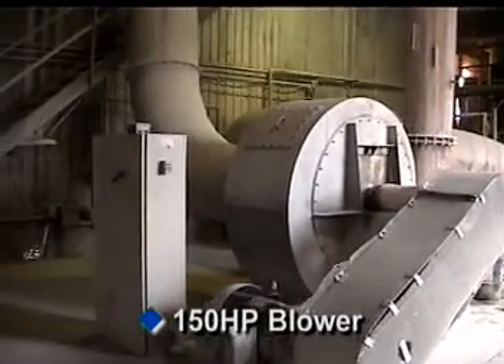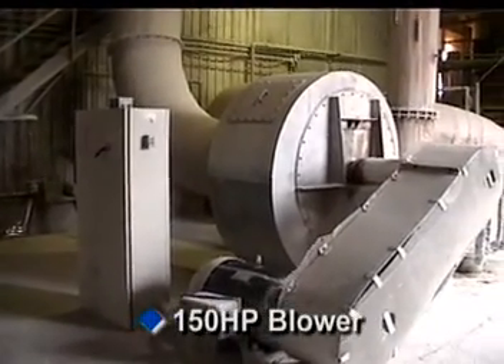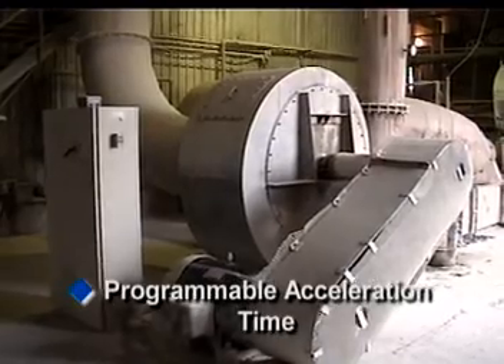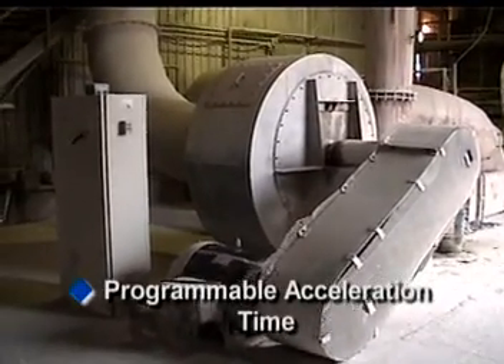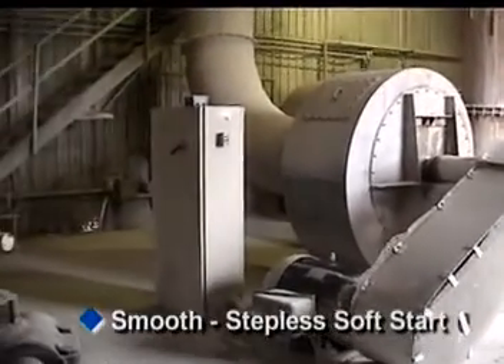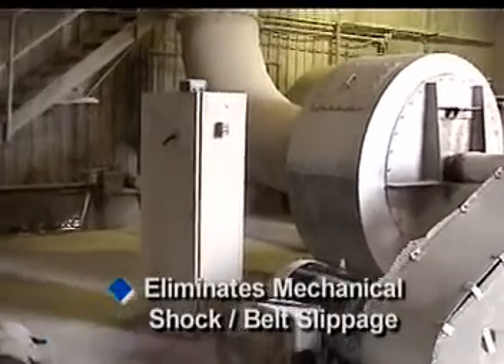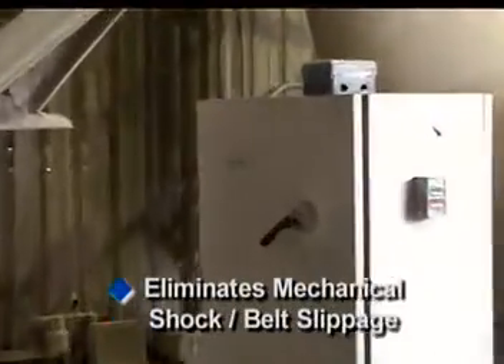At this site, a 150 horsepower blower is controlled by a Benshaw solid-state motor controller used to eliminate mechanical shock and belt slippage, as well as reduce the inrush currents associated with starting a fan of this size.